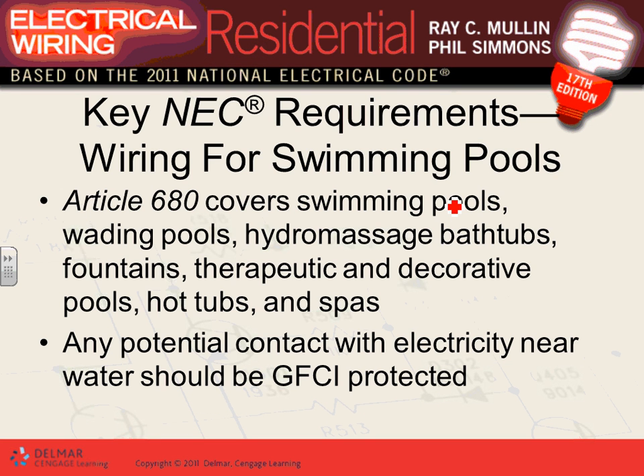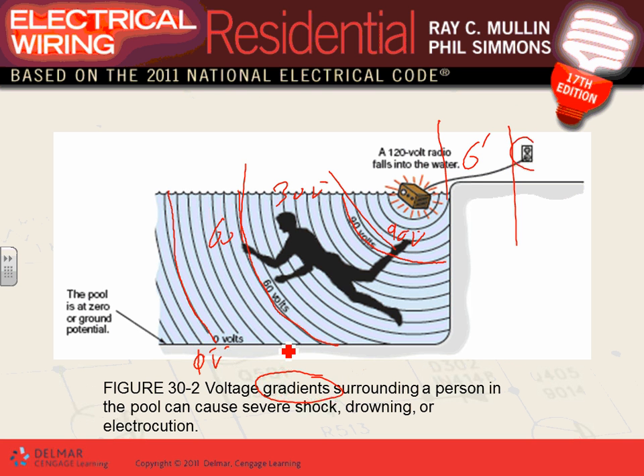Voltage gradients. Okay. The NEC code book, guys, has a whole article, 680, that talks about electrical wiring in a swimming pool and hydromassage bathtub and wading and all these places where you can have people in water. So there are all these hot tubs and so forth. Potential contact with electricity. So you can imagine the importance of a GFCI there. So for example, if this is a GFCI circuit breaker, the minute that you drop that radio in the water, guess what's going to happen to the GFCI? Trips. You can imagine the importance of a GFCI.